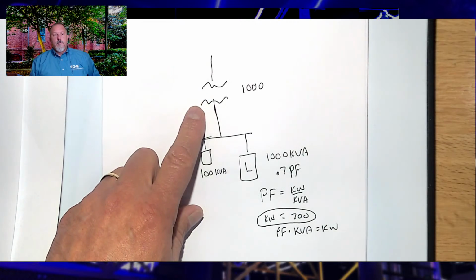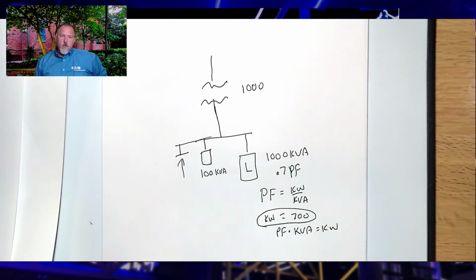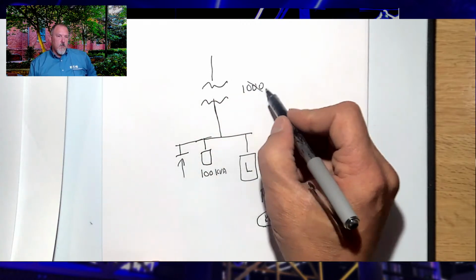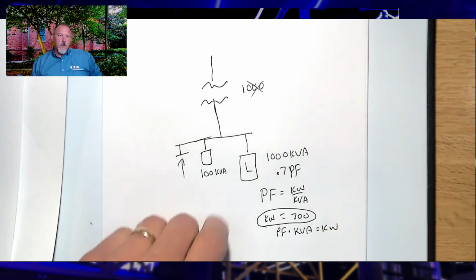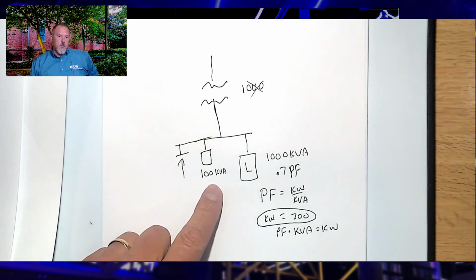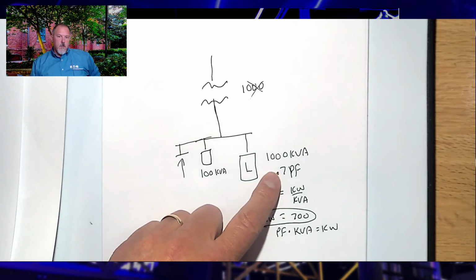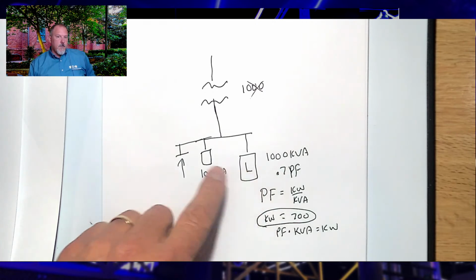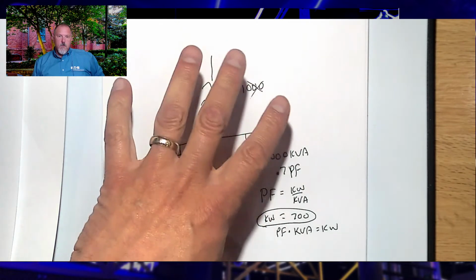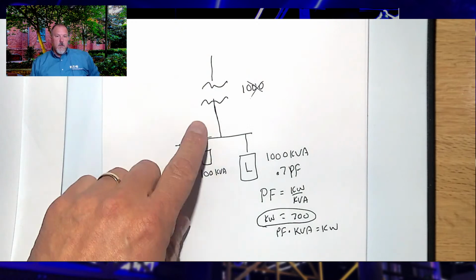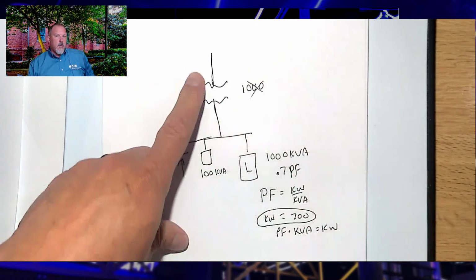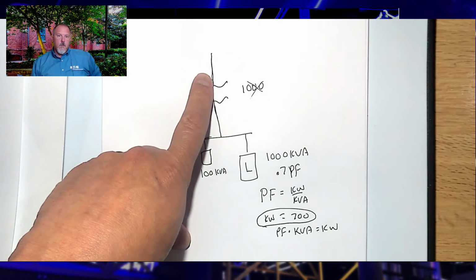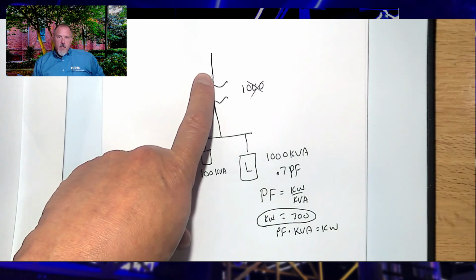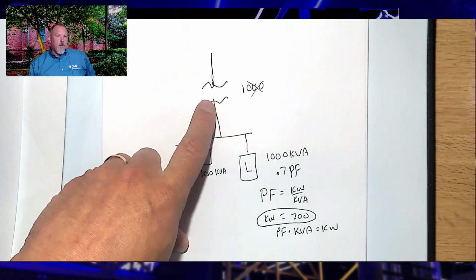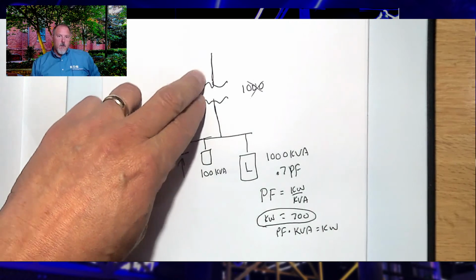So you call them up and you say, hey, give me a 1,500 kVA transformer, and you know what they're going to say? No. How about you put capacitors in there, or we're going to bill you $2,000 a month until you fix your power factor, because you're using capacity of my wires. And again, what are wires rated in? Amps. What are amps proportional to? kVA. They're not proportional to watts either. So all my devices are rated in either kVA or amps.